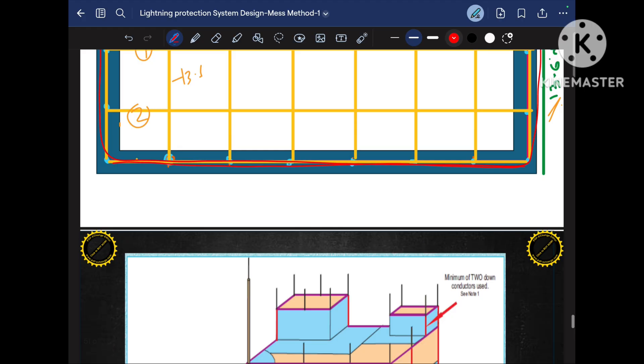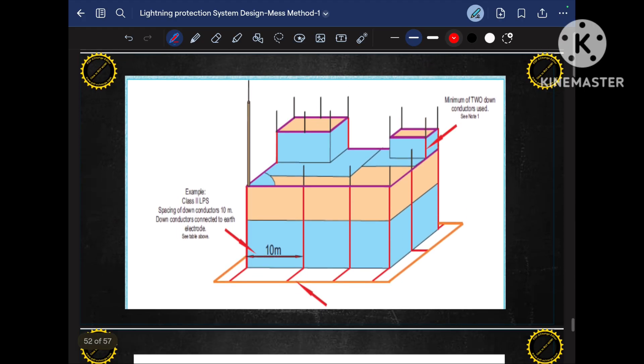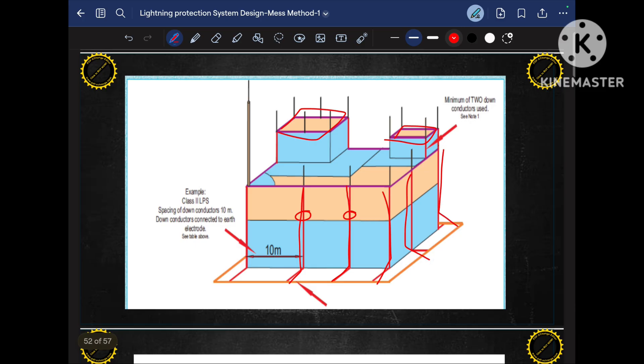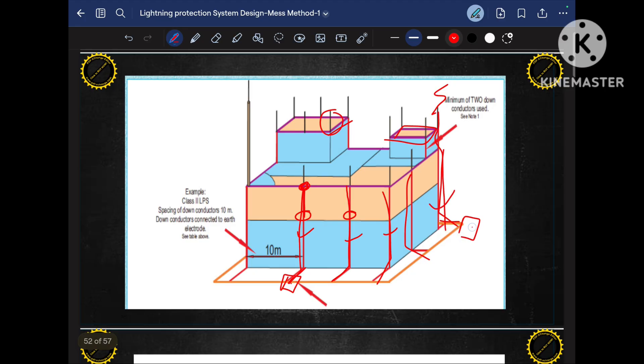Now we have to determine the down conductors. Let me explain what a down conductor is. We calculated this MESH, but this MESH needs to be connected to the earth pit — this is done through down conductors, which are all the vertical runs. The function of the down conductor is to provide connection from the MESH or lightning arrester to the earth pit, running from the top to the bottom. If any lightning strikes the air terminal rod, it will travel through the minimum resistance path via the down conductor directly to the earth.